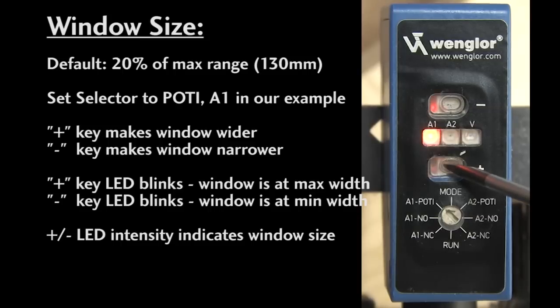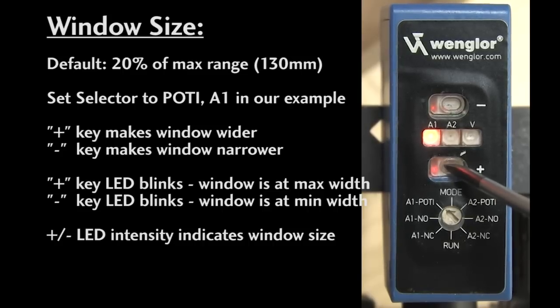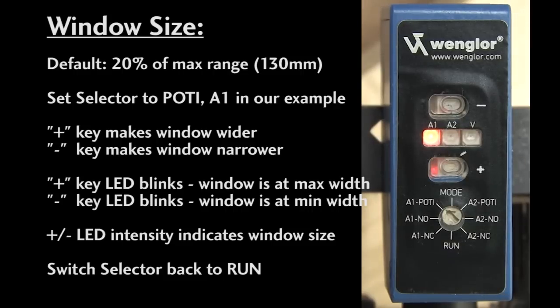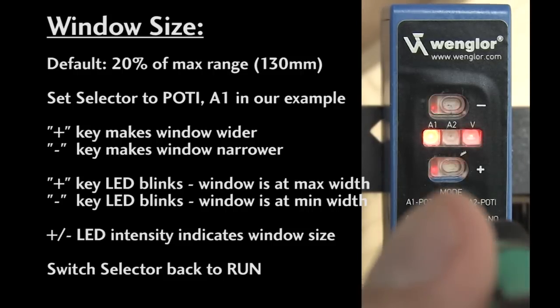It's a little hard to see in this video, but the intensity of the LEDs changes as you get closer to the limit. The closer you get to the widest window, the brighter the plus LED gets. The closer you get to the minimum window, the brighter the minus LED gets. I've found there's a little over 50 button presses between the max and the min. You can also hold the button down and let it gradually change. Once you get the window you want, switch the selector back to run.